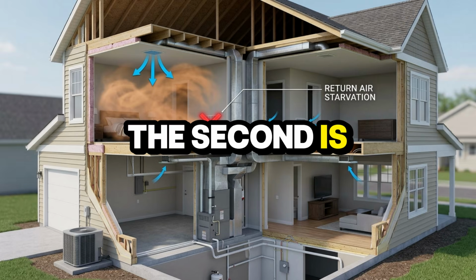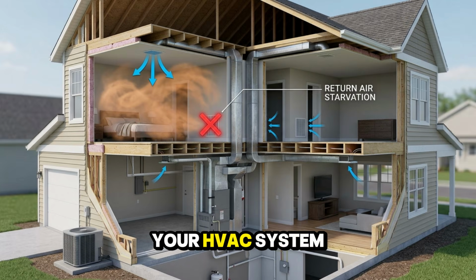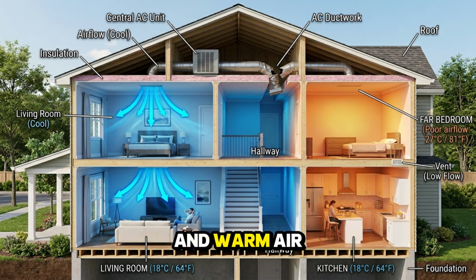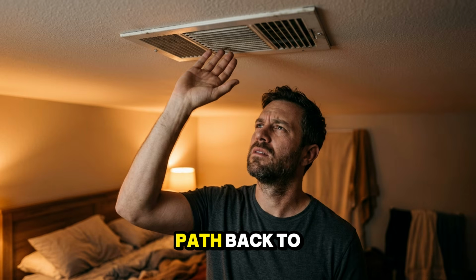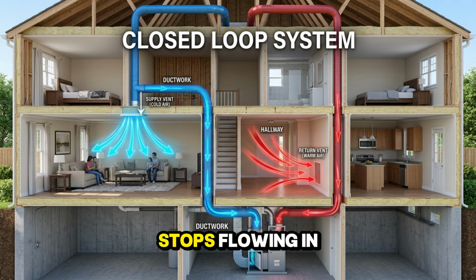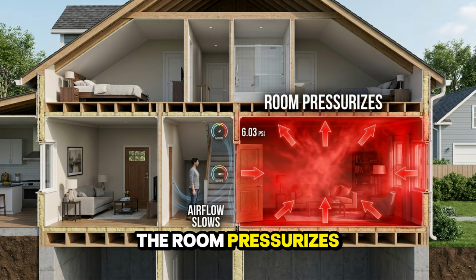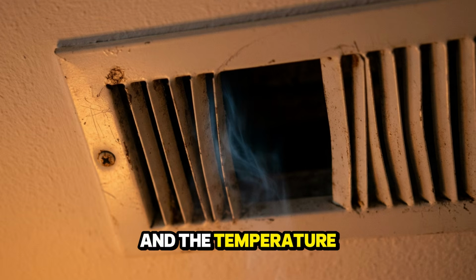The second is return air starvation. Your HVAC system is a closed loop. Cold air goes out through supply vents and warm air has to come back through return vents. If the warm air in your hot room has no clear path back to the system, the whole loop breaks down. New cold air stops flowing in efficiently. The room pressurizes, the airflow slows, and the temperature climbs.